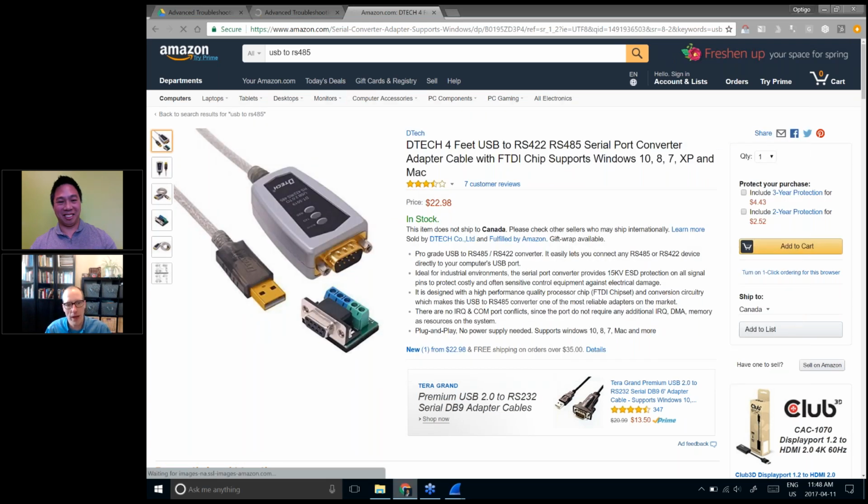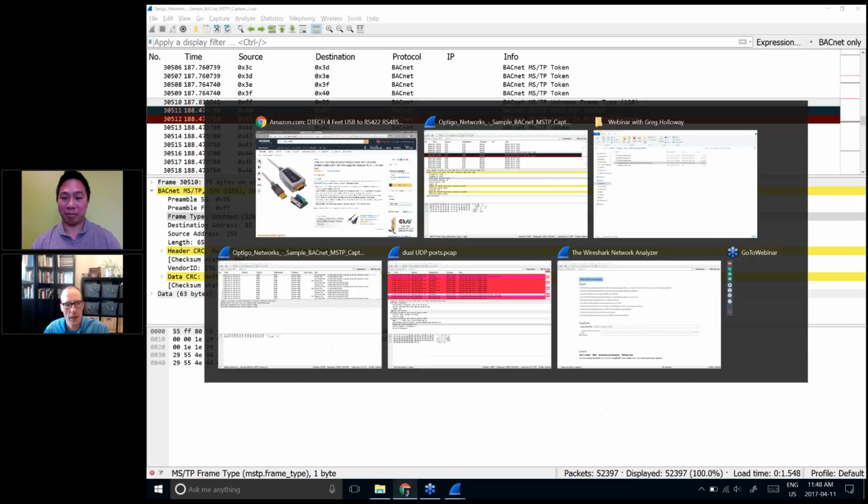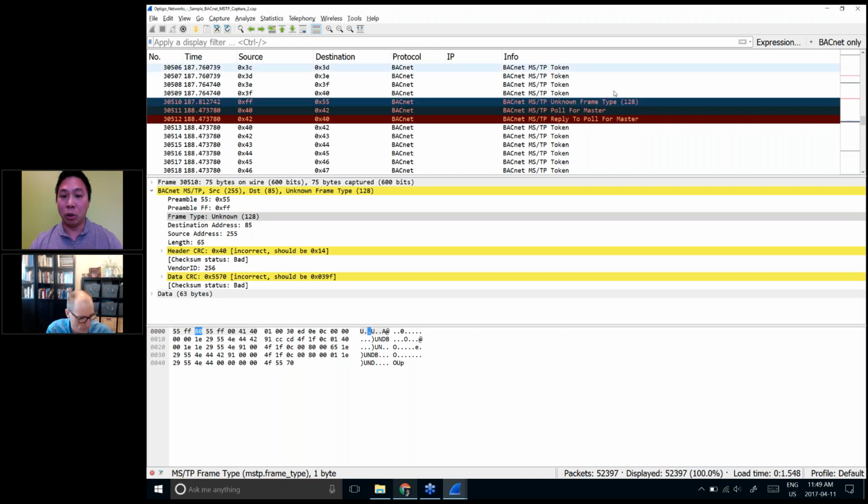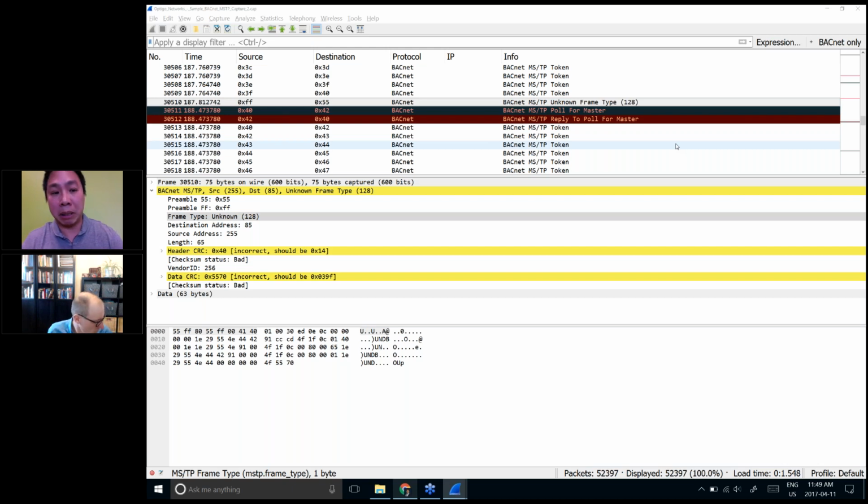If you're looking for a token problem, that kind of thing, token handling, you really have to capture at the MSTP level. You can't capture at the Ethernet level because it's not going to show you anything. If you think all that's too much trouble, talk to Ping about Contemporary Controls because they've got an agreement with those folks. Right, Ping? Yes. So Contemporary Controls, and actually I can tell you also, we're working with a few other manufacturers. We're encouraging manufacturers to add capture functions into their MSTP routers because we do know that capturing the data is a first phase that's a little bit difficult. But Contemporary Controls has a router called the BAS router LX that has a built-in capture on the MSTP side of the router. So it's a simple little tool they can use to capture things on the MSTP side.